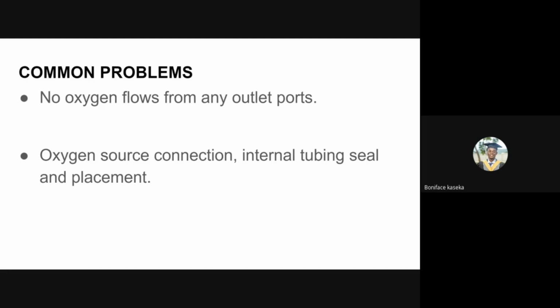So the first common problem that is encountered is when you have no oxygen flow from an outlet port. It could happen that you want to use an oxygen flow splitter and you have opened using the knob, but you're not getting any oxygen from the outlet or any other outlet port. So the possible cause for such a problem could be that there's a problem with the oxygen source connection. When we talk about the oxygen source connection, you are talking about either the oxygen concentrator, the piped oxygen, or the oxygen cylinder. So if there's a problem with the connection between the oxygen concentrator and the inlet of the oxygen flow splitter, then that means the oxygen flow splitter will not be getting oxygen.